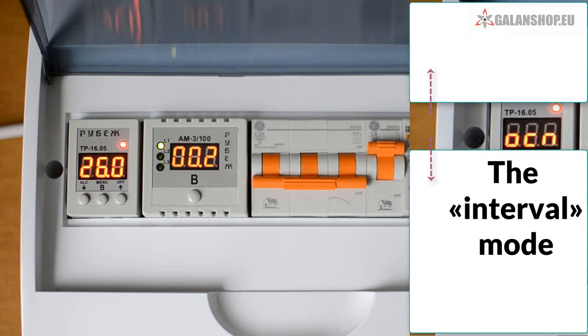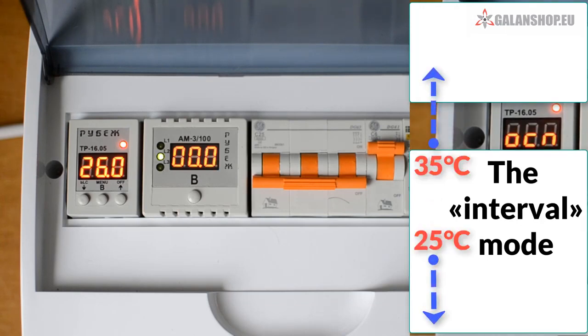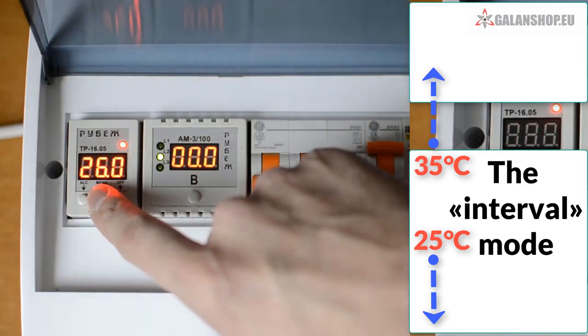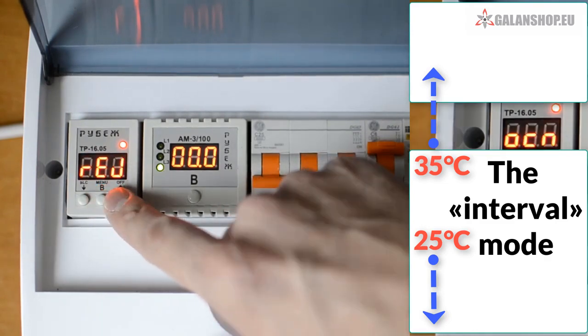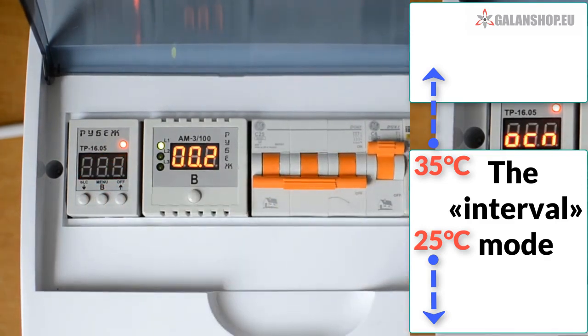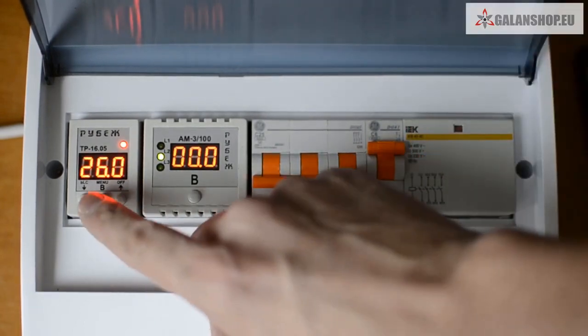The third mode, interval mode: if the requested temperature is set to 30 degrees and the hysteresis is set to 5 degrees, the controller will make it turn on in the range of 25 to 35 degrees and will make it turn off if the temperature is above 35 degrees or below 25 degrees.